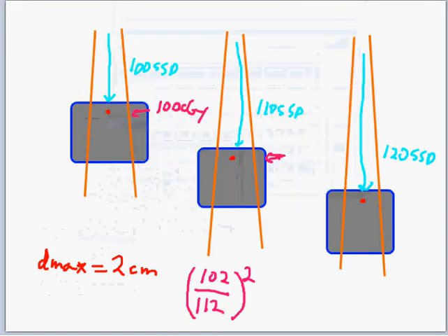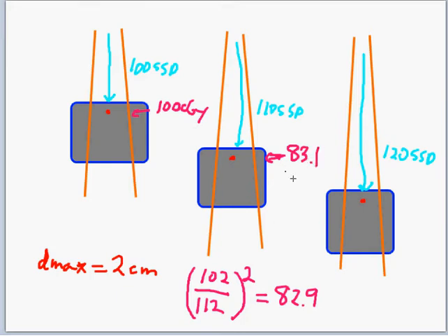So that's what we're expecting to get at that point, 82.9 centigray. Let's say you try this out when you commission the machine, and it comes out pretty close to that, say it's 83.1. Maybe it's not exact, but it's close enough that we can say inverse square seems to work in that case. How about this one over here?